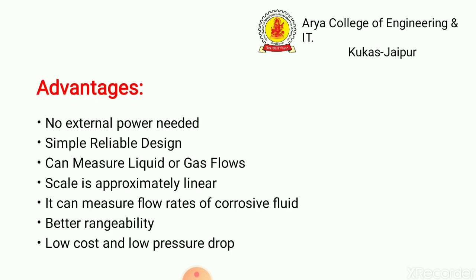Some advantages of Rotameters: no external power is needed; simple and reliable in design; can measure both liquid and gas; the scale is approximately linear; low cost; it can measure the flow rate of corrosive fluids; better rangeability; and low pressure drop.